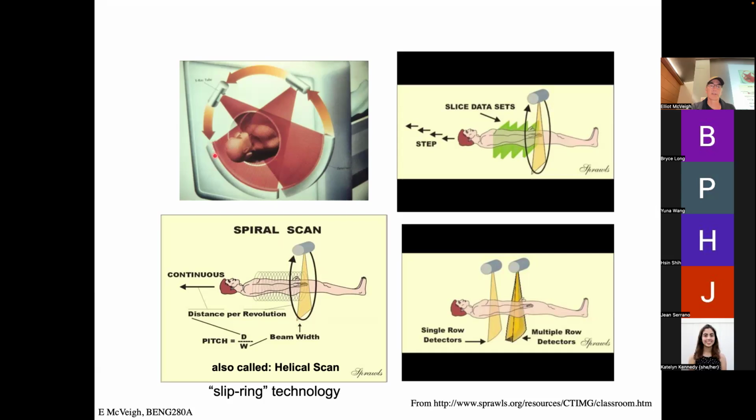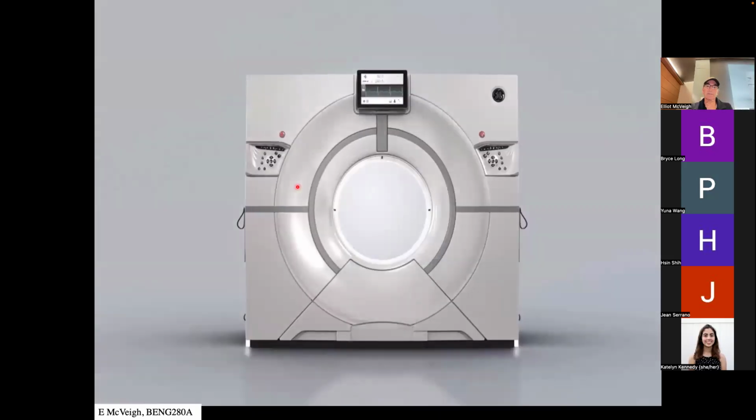Siemens did another clever thing. They put 2 X-ray sources in the gantry and a detector here and a detector here. So they essentially increase their angle of sampling, or they basically got 2 CT scans done at the same time at 90 degrees, right? So basically they could get the data twice as fast with that as well.